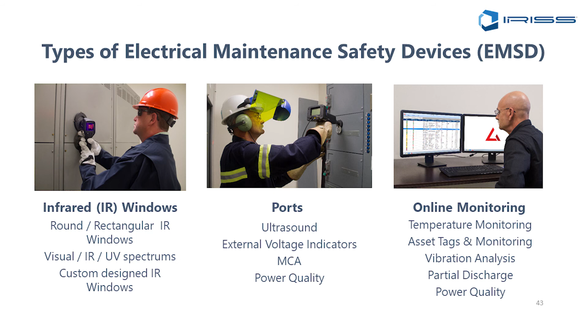So you've got temperature monitoring, partial discharge monitoring, power quality, vibration. There's permanently installed vibration monitoring that's a fairly common thing now. So different types of windows for looking and listening to the gear. We make all kinds of different kinds, whether visual, infrared, ultrasound capable, either with a ultrasound little port that swings open that lets you listen into the gear.